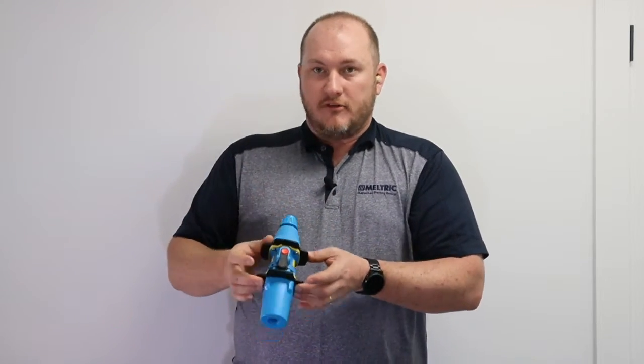And that's a unique feature to Meltric in that when you do that, you're actually still able to contain all of those things. In a pin and sleeve that operates on a straight insertion kind of method, if you do have that kind of explosion that happens from closing on a fault, you risk having that plug shoot back out at the user, and then any arcing that happens comes out as well. So it's kind of an interesting thing we don't talk very much about, but that capture of closing on a fault and containing that arc is also something that's pretty unique to a Meltric device.